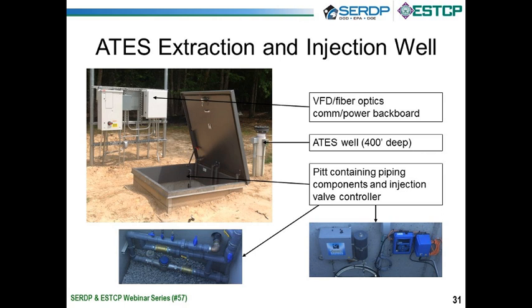In the upper right-hand corner of that lower right picture is the actual controller, where we're monitoring GPM, pressure, and valve position, and we're putting the injection valve where it needs to be. We don't want to put unnecessary back pressure on the system, but we also do not want to let the water ever be unpressurized. We don't want to create a vacuum. You don't want to squirt the water in at the top of the well and hope it somehow gets down to the bottom before it gets oxygenated. When it gets oxygenated, perhaps if there's iron in there, it precipitates out. And then there's bacteria that love the iron precipitate, and then you have biofouling.